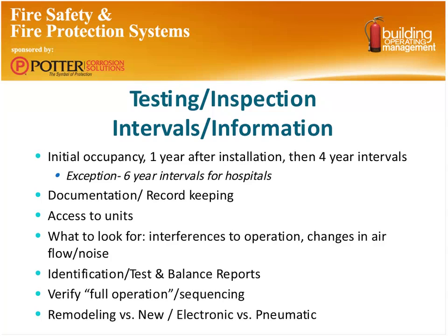What to look for? Typically you're looking for interferences to operation, changes in airflow, and noise. In addition to that, verifying that there's full operation and sequencing. When we do that, typically we're doing that in conjunction with the fire alarm provider, because most of these systems are integrated with the fire alarm so that the damper will control during a fire event. There are some cases where the dampers actually have a test switch, and in that case the fire alarm contractor doesn't need to be involved, just a mechanical contractor by himself. So the point being, there may be some coordination that you as the building operator have to take on to make sure that these two entities are working together to get this full function and inspection completed.